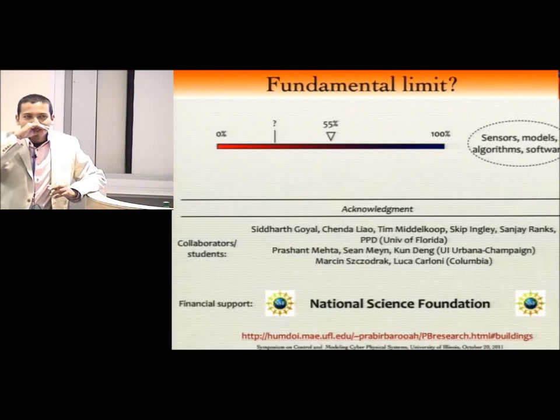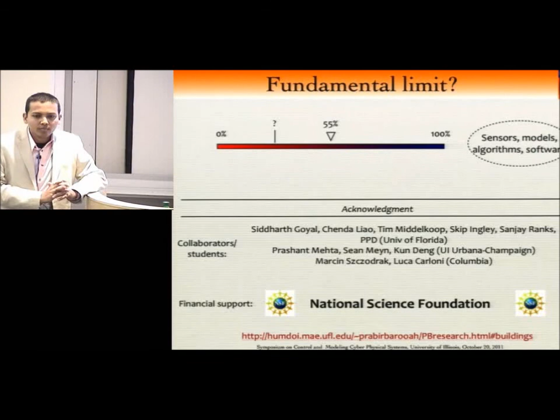Follow-up question: I agree the main culprit for energy consumption in buildings is HVAC, but specifically if you look at VAVs and reheat coils, what percentage do they contribute to total HVAC consumption? Because another factor is the pumps that circulate air, they use a lot of energy because they're motors running continuously, whereas reheat only runs briefly, a couple of minutes, five times an hour or once every half hour or so.